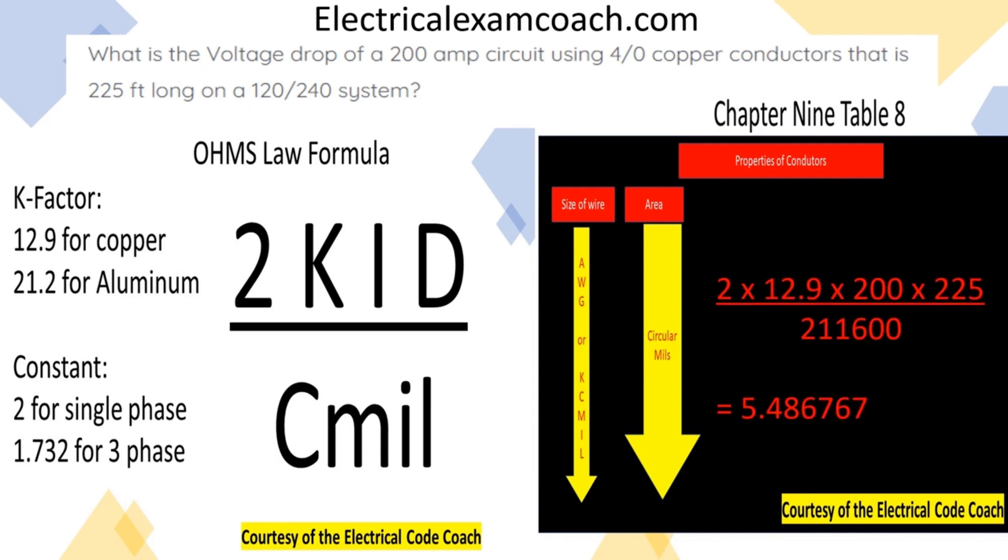After we work out all our math, and this is what I love about formulas. Just plug in what you know and then spit out the answer. 2 multiplied by 12.9 multiplied by 200 multiplied by 225 divided by the circular mills of a 4-aught copper conductor.